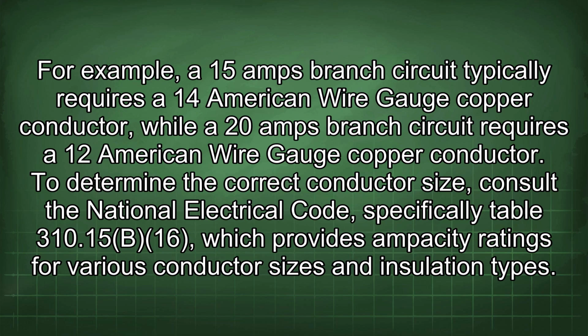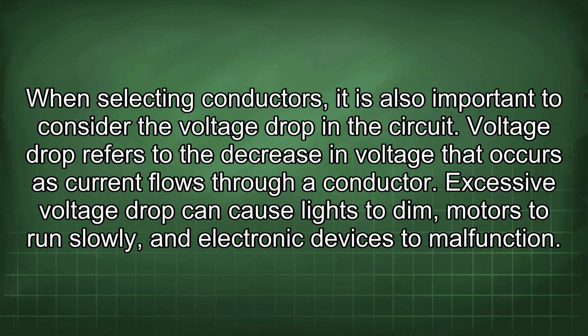To determine the correct conductor size, consult the National Electrical Code, specifically Table 310.15(B)(16), which provides ampacity ratings for various conductor sizes and insulation types. When selecting conductors, it is also important to consider the voltage drop in the circuit. Voltage drop refers to the decrease in voltage that occurs as current flows through a conductor. Excessive voltage drop can cause lights to dim, motors to run slowly, and electronic devices to malfunction.